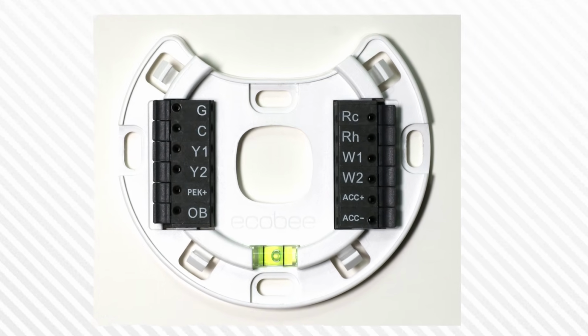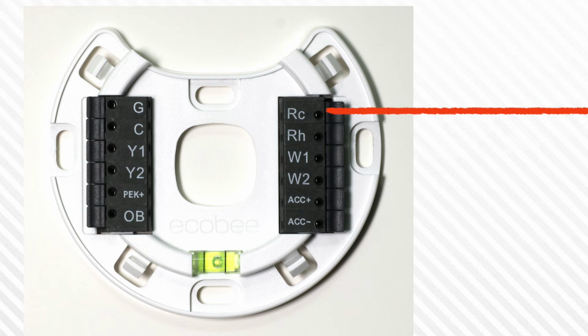So if you only land a single wire on that RC terminal, the thermostat's going to know you're either running a straight cooling system or a combination system with only one transformer in it, and it's going to use that jumper. If you run wires to both R terminals, the thermostat's going to know you're running two separate systems and it will deactivate that jumper.